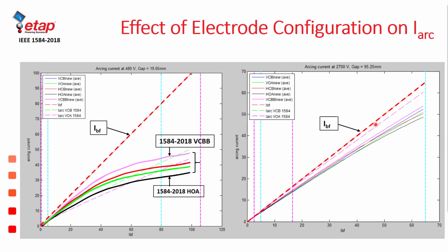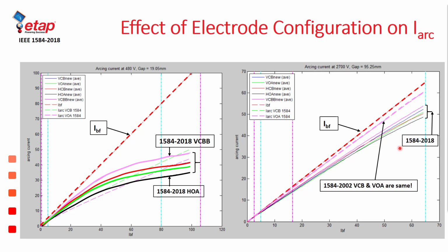We know that it is physically impossible for an arc flash within an enclosure and outside of an enclosure in open air to yield exactly the same amount of arc current. The presence of the box and the enclosure will change the length of the arcs, and therefore the arc resistance and the arc current magnitude. We can see that that behavior is not expected physical arc behavior.